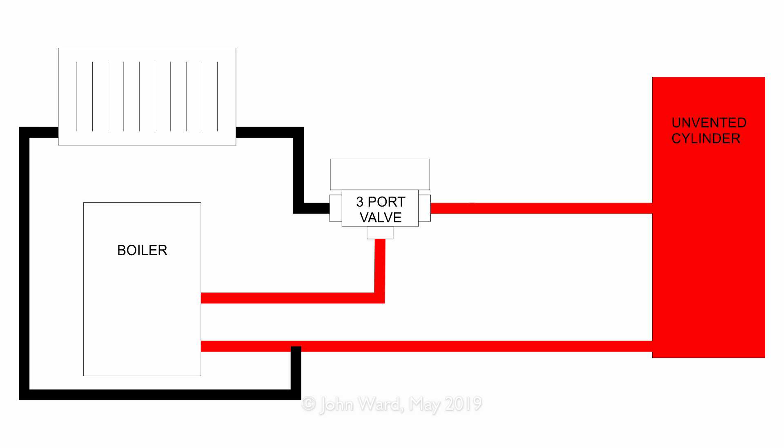And the end result would be that the cylinder would get dangerously hot, and of course when you heat water it expands, and in a closed and pressurized thing like an unvented cylinder, that can build up to a very dangerous level. And although there are of course safety devices on the cylinder to vent out any excess pressure and whatever, the point is that's not supposed to happen at all, and in the worst case scenario the cylinder could obviously explode and turn into a giant bomb, so obviously that's something that needs to be avoided.